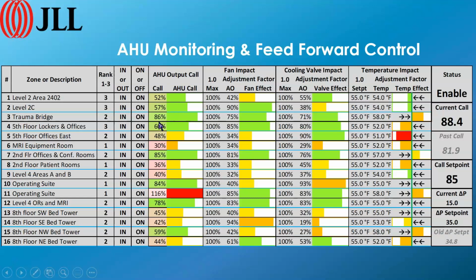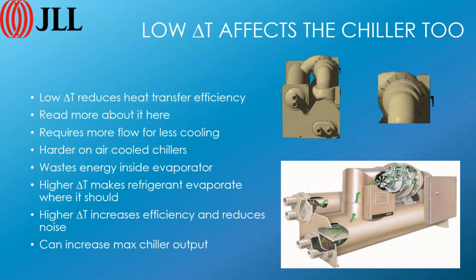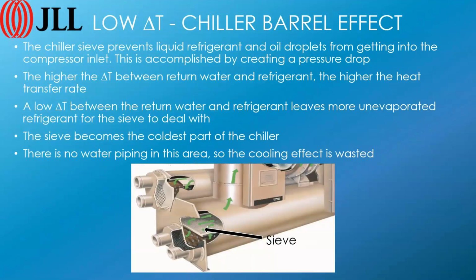So we're really trying to get away from having a bunch of PID loops happily waving up and down all over the place and eventually living with the outcome of that. And we're trying to use this information to inform how much water we want coming out of the chilled water plant. It affects the chiller quite a bit. That low delta T affects the chiller, and we want to really pay attention to that. That is the other thing that happens sort of accidentally. And I'm going to just move on to the next slide and show you where that's coming from.